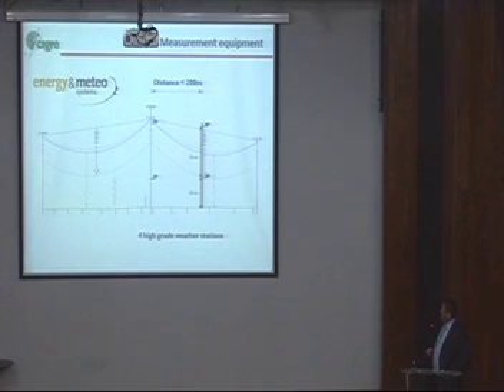Another case to demonstrate the variability of wind is from a two-span section that was done in Germany. We have weather stations, from a Meteorological Institute which did these measurements. It was presented in CIGRE 2003 in Australia. They had weather stations on a suspension tower and a met mast, which was about 200 meters away, and they compared wind speeds measured over the short distance.